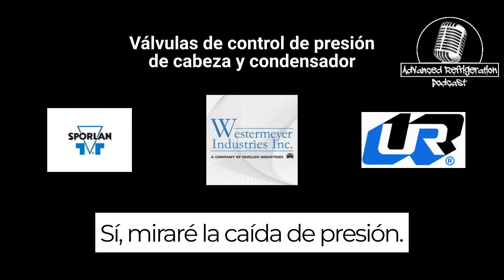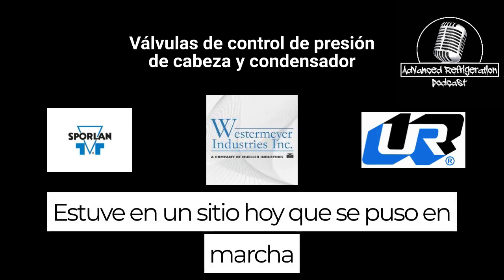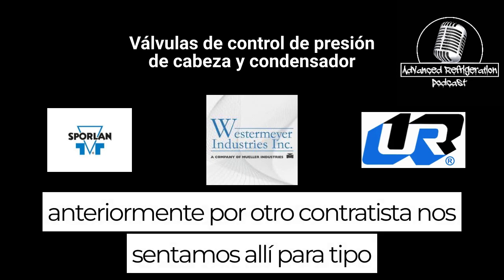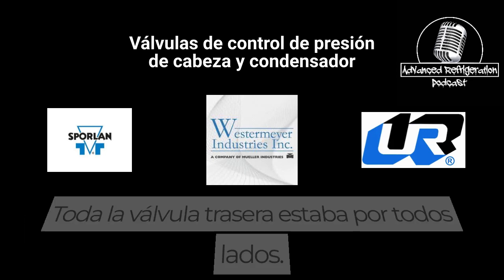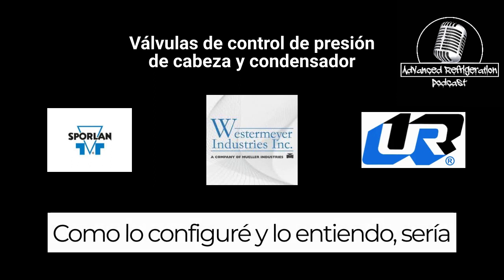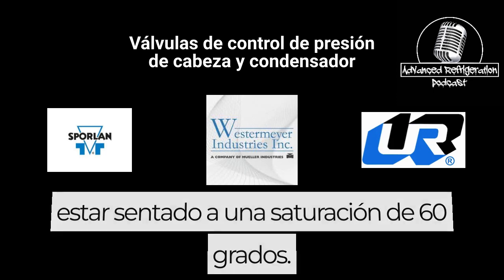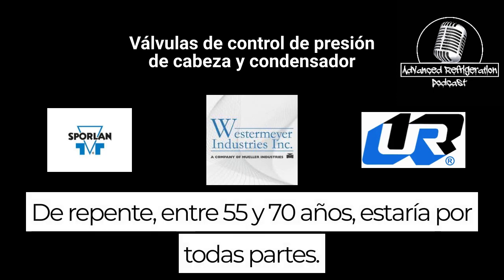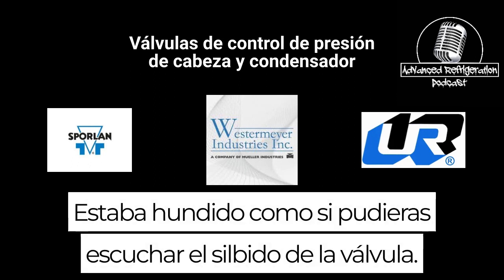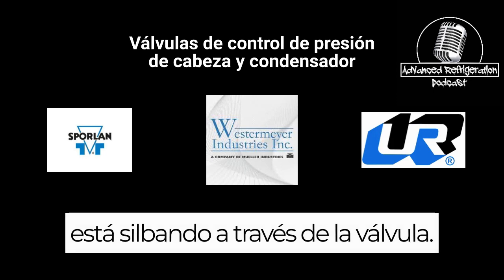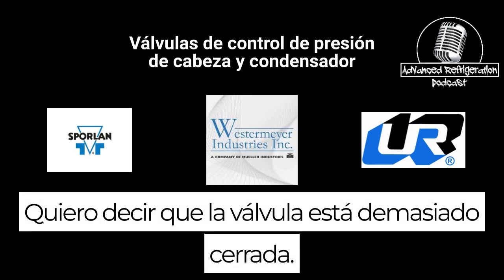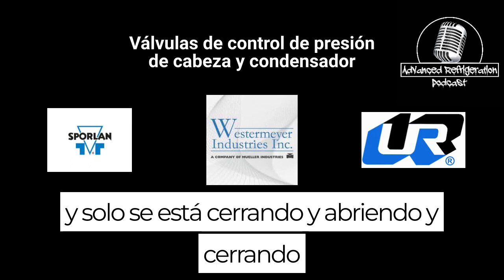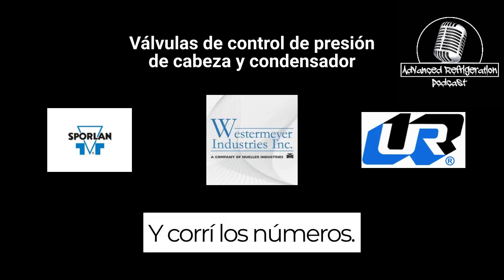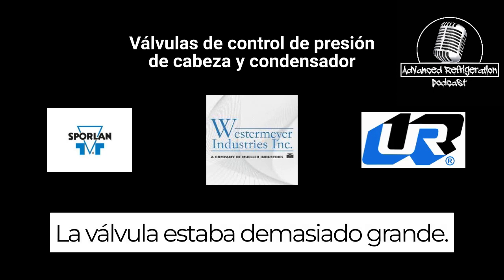Yeah, I'll look at the pressure drop, but if I was at a site today that was started up previously by another contractor, and we got sent in there to clean up the mess, and before the store opened, the whole back valve was all over the place. I'd set it, and it'd be sitting at like a 60 degree saturation, and all of a sudden it'd be 55 to 70. It was hunting. You could hear the valve whistling. I know right then and there, it's whistling through the valve. The valve is too part closed, and it's just shutting and opening, shutting and opening. And I ran the numbers, and the valve was way oversized.